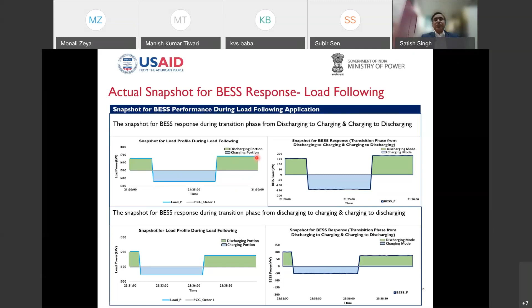So again, if the actual load power is something like this, this is how your battery is responding. In case the load is more than the set value, the battery is discharging, and again there is a toggle whenever this value is changing. This is charging mode when the value is less than the set value. So load following is important when we want to firm up to follow a particular load, using a battery to obtain a very fixed amount of output from the grid perspective and also from a load demand perspective. Whenever there is a variation in your load, the battery absorbs those variations so as to provide a very clear output.